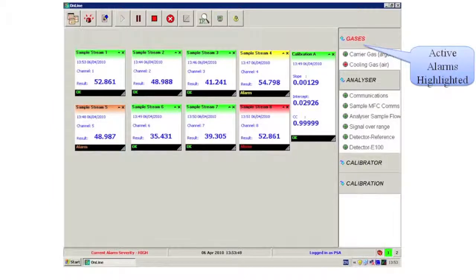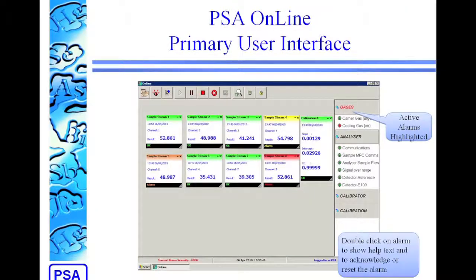Going back to look at the grouped alarm displays again, the name of each group will go red to show that an alarm within the group has been activated. And if you expand the group, the little colored dot next to each alarm will show the alarm status for that. So again, green is no alarm, and yellow, orange, or red for low, medium, or high. And if you double-click on any of the alarms, it will show you the help text, and you can acknowledge or reset the alarm from there.